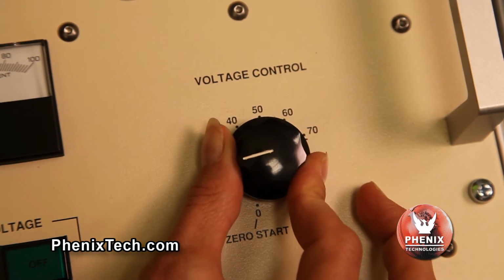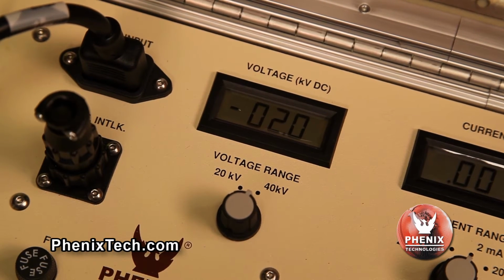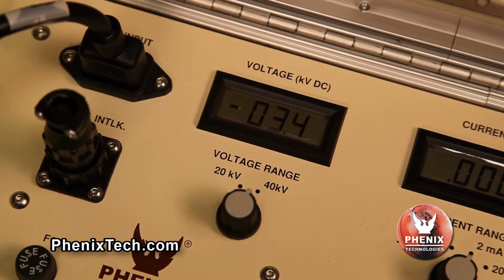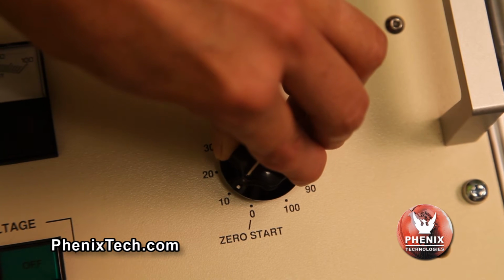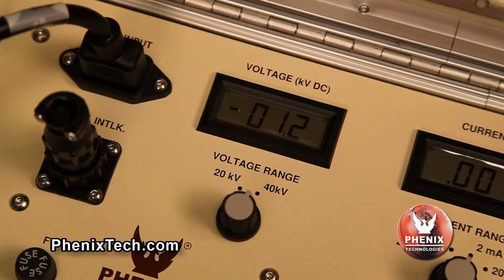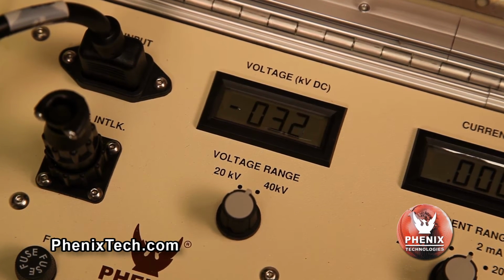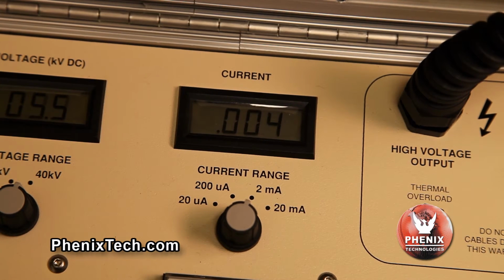Rotate the voltage control dial and watch the output voltmeter increase until desired voltage level is reached. The voltage control knob is calibrated in % of voltage range selected. With the voltage control knob at the 10% position and the voltage range selector switch at 40 kV, the test set output is approximately 4 kV for the model 440-20. Current meter will read resulting current. Record data if desired.